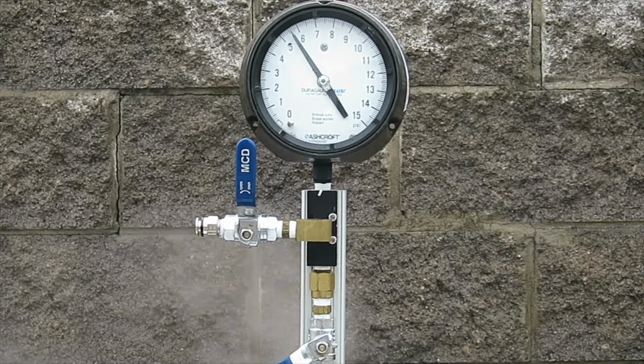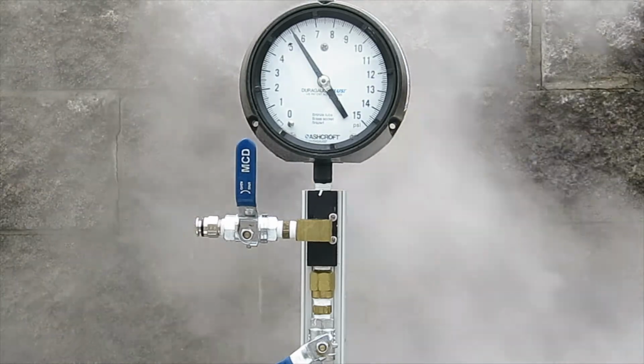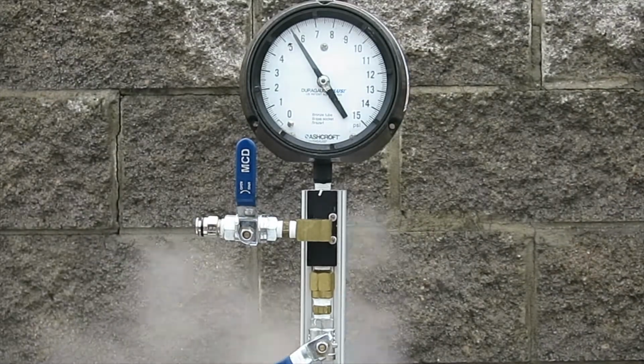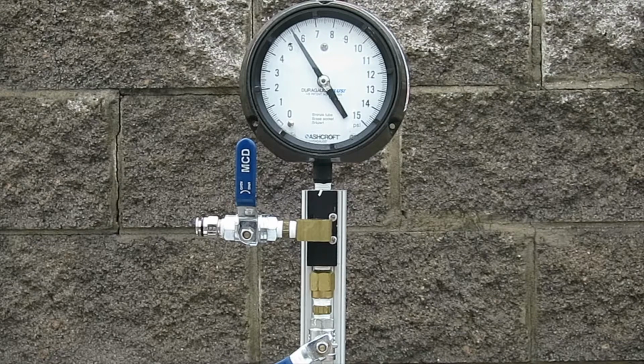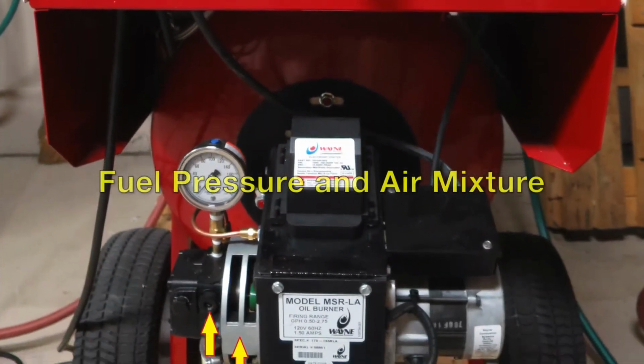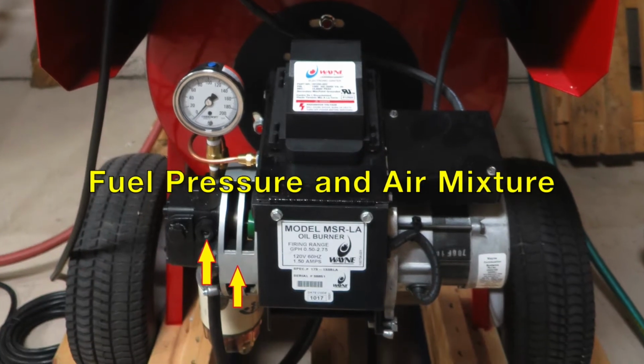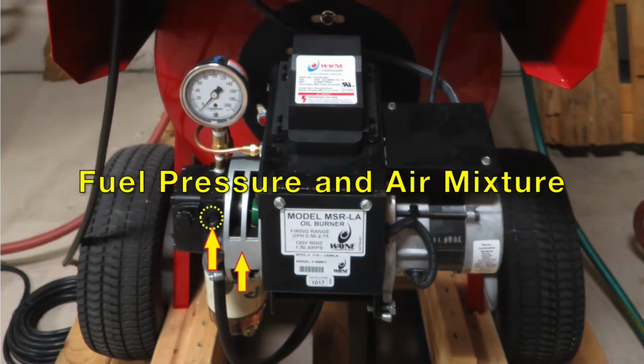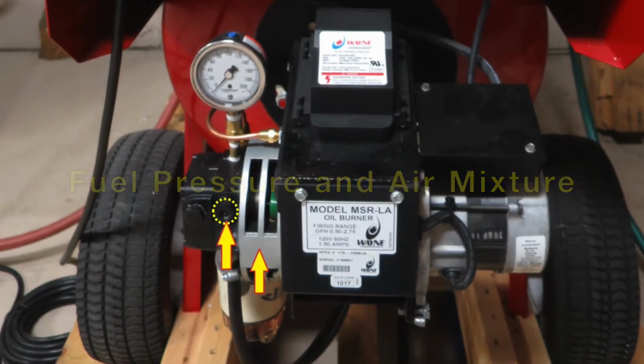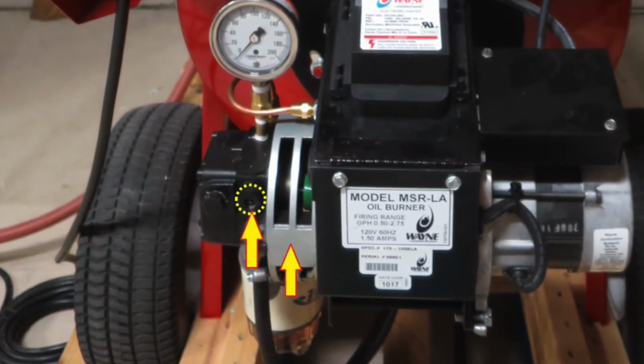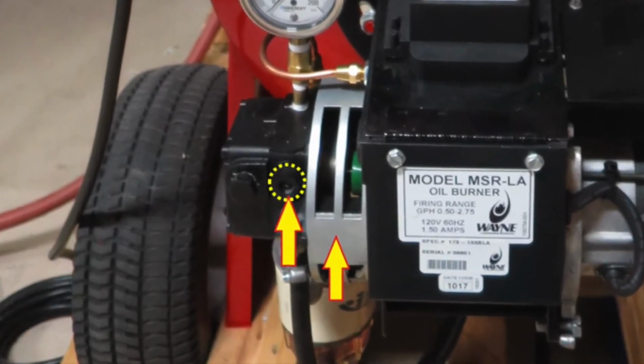If the dynamic head pressure is too low, you will be raising the fuel pressure. If the dynamic head pressure is too high, you will be lowering the fuel pressure. The fuel pressure adjustment screw is shown in this picture from the Getting to Know Your Equipment section and is directly above the left arrow. Remember to take note of pressure before making an adjustment. You may need to return to that pressure.